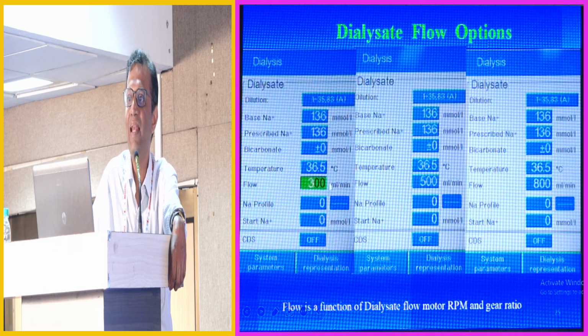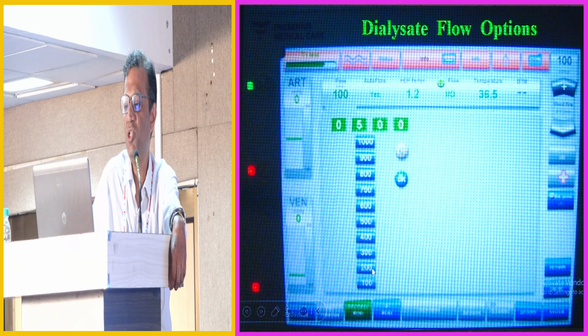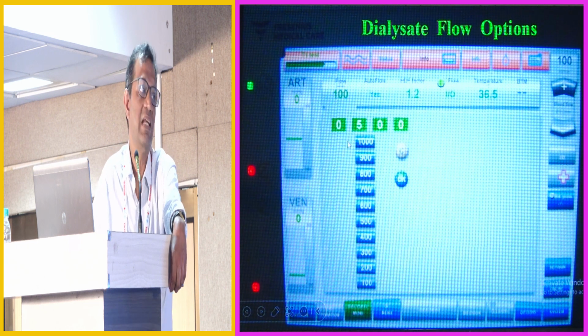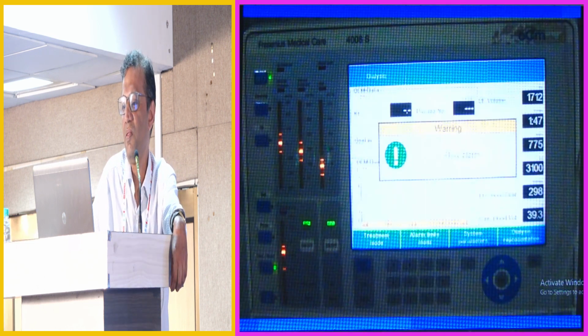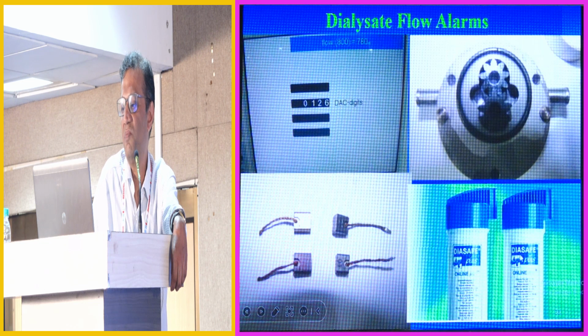Now this is the dialysis menu of the 4008 machine. It can have flows of 300 ml per minute, 500 ml per minute, or 800 ml per minute. If you have a 5008 machine, you can adjust the flows all the way from 100 ml per minute to 1000 ml per minute in increments of 100. Now this is something that you will see, this warning on the machine often: flow alarm. Why does this happen? There are 4 possible reasons.